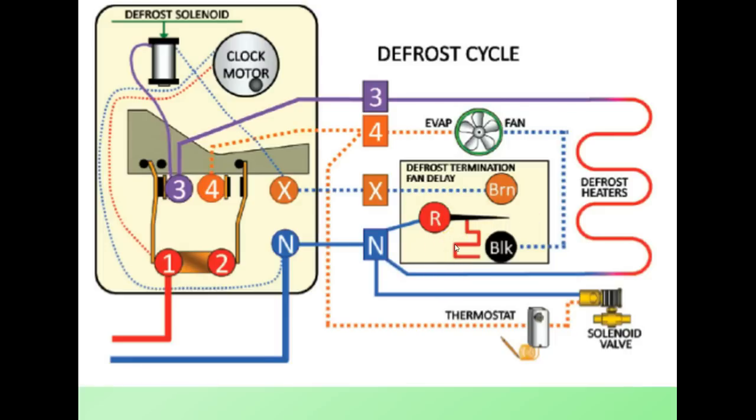As we're melting the ice off of the coil, the temperature of that coil begins to rise and our defrost termination fan delay is sensing that temperature rise and is slowly moving this contact up as the temperature increases.